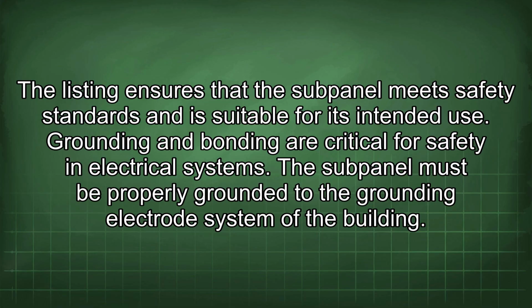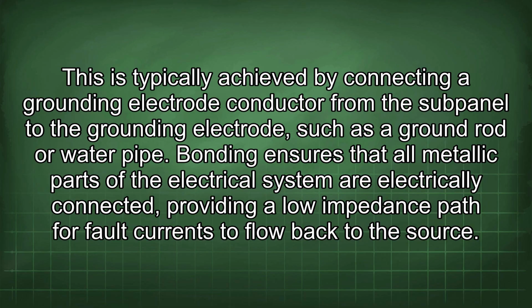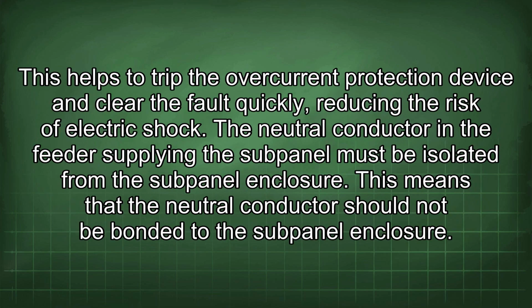Grounding and bonding are critical for safety in electrical systems. The subpanel must be properly grounded to the grounding electrode system of the building. This is typically achieved by connecting a grounding electrode conductor from the subpanel to the grounding electrode, such as a ground rod or water pipe. Bonding ensures that all metallic parts of the electrical system are electrically connected, providing a low impedance path for fault currents to flow back to the source. This helps to trip the overcurrent protection device and clear the fault quickly, reducing the risk of electric shock.